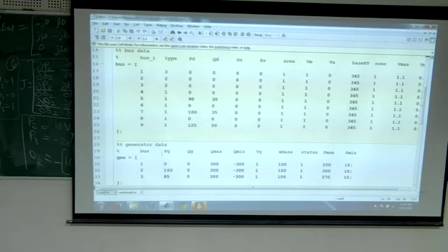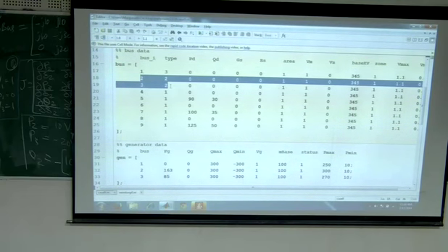Now I'll ask you the question: how many state variables? 9 buses, therefore 18 state variables. Out of 18 state variables, how many are known, and how many are unknown? For the slack bus, you know both voltage and angle. If you look at 2 and 3, you know voltage, but you don't know the deltas. So two are unknown. Whereas the remaining 6 buses, 6 times 2 is 12 unknowns. So 12 plus 2, 14. There are 14 unknowns. So the size of your Jacobian matrix will be 14 by 14.